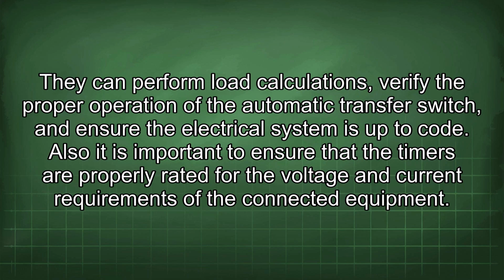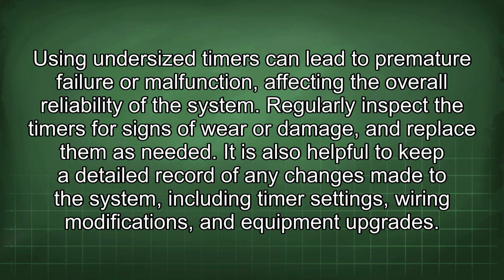They can perform load calculations, verify the proper operation of the automatic transfer switch, and ensure the electrical system is up to code. Also, it is important to ensure that the timers are properly rated for the voltage and current requirements of the connected equipment. Using undersized timers can lead to premature failure or malfunction, affecting the overall reliability of the system. Regularly inspect the timers for signs of wear or damage, and replace them as needed.